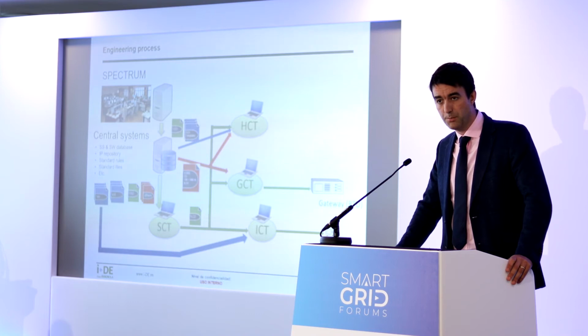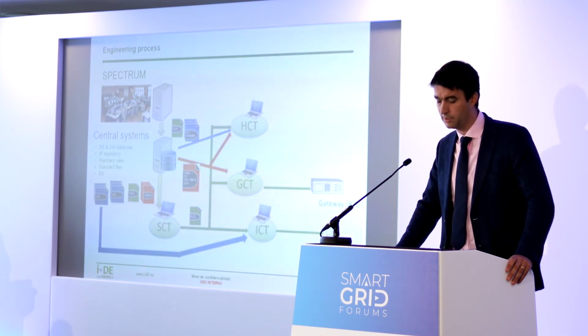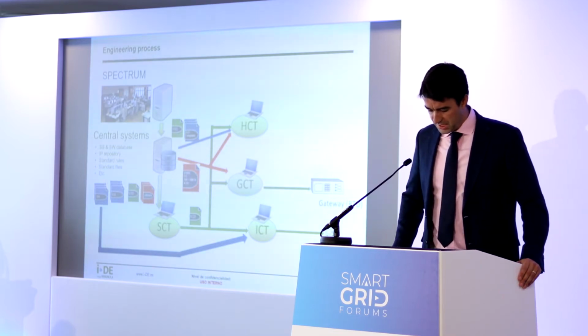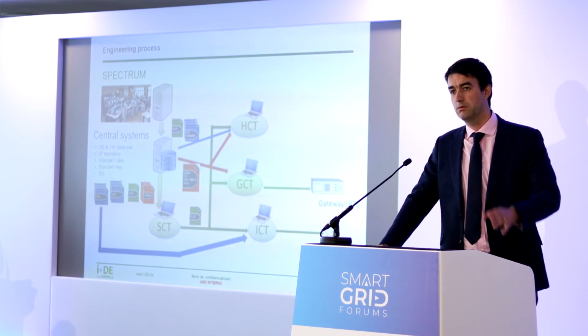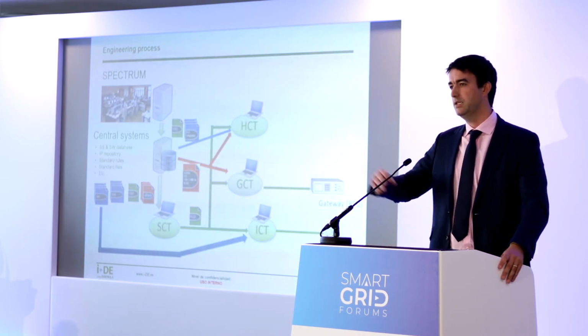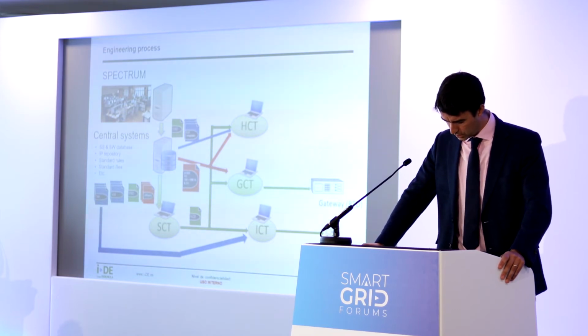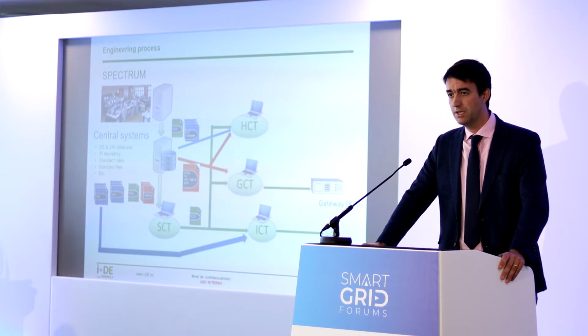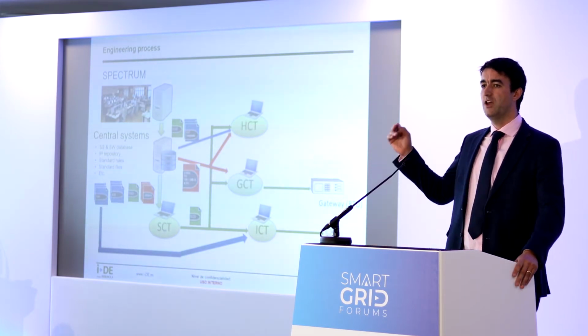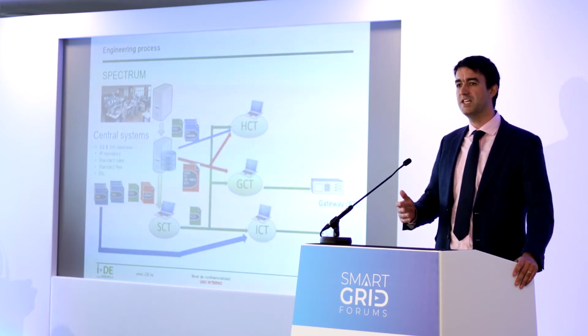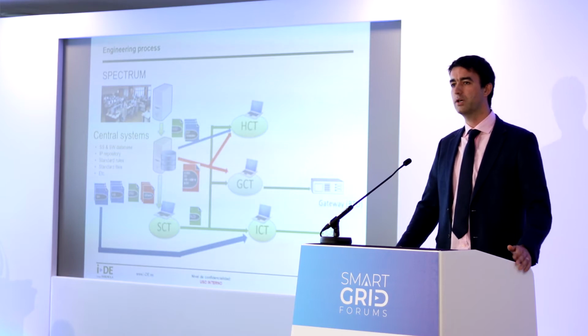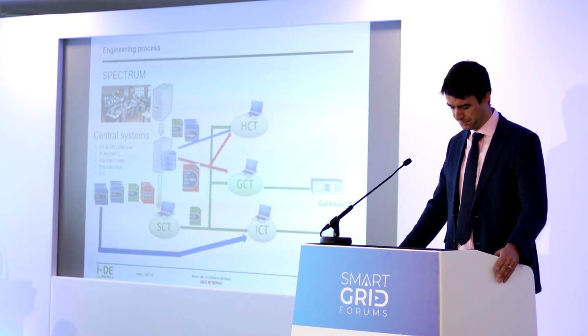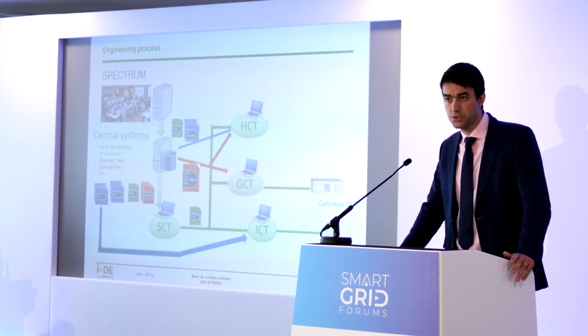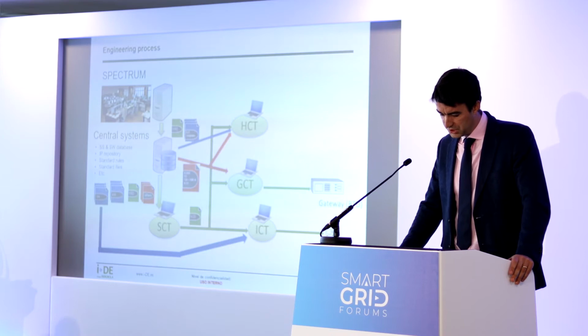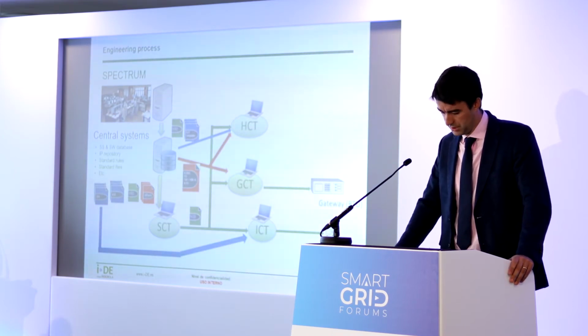This database essentially does two main things. It houses all the repository of our standardized information, including ICD templates, where it receives all the information that is consistent between the same IED and the same bay type in different substations. But it's also what's going to receive the information that is particular to that substation. It's going to receive information from our GIS and our SCADA systems. It's going to receive the single line diagram, interpret it, and know what kind of bay types are going to be for this new substation. And this means that our central systems will have all the information which is consistent per bay type, as well as what is particular to that substation.